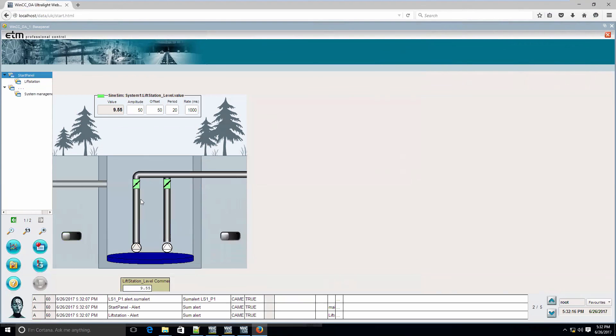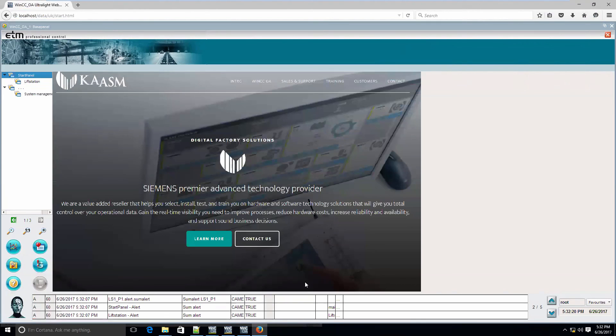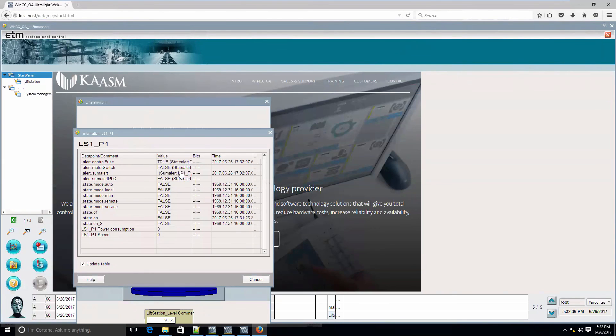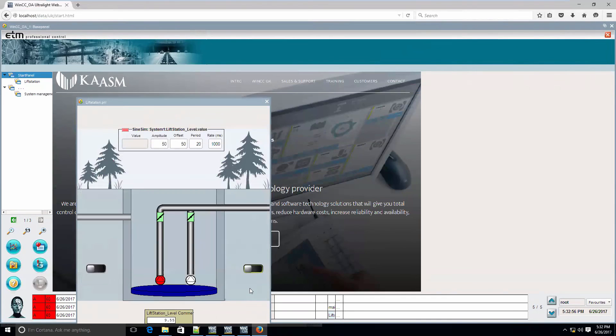Notice as soon as that alarm came in, I got a flood of alarms inside my alarm alert viewer. If I happen to not be on the particular panel generating this alarm, I see an alarm notification come in and can open that panel directly. One right mouse click, two — there are my two active alarms. That's less than three clicks to get into the actual alert variable, conforming to the ISA-101 standard. This concludes the demo — we used a lot of predefined stuff and turned the creation of a brand new project into a fully functional runtime engine with simulations.